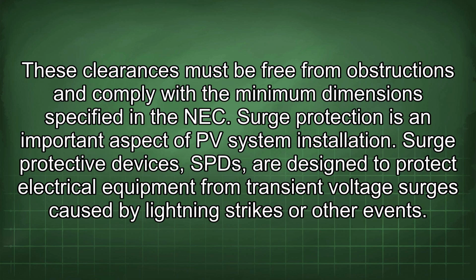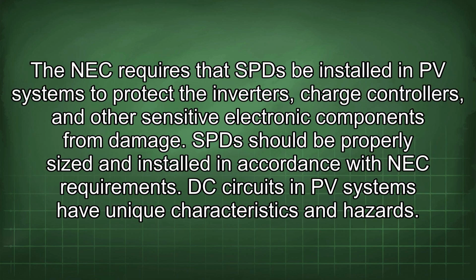Surge protection is an important aspect of PV system installation. Surge protective devices, SPDs, are designed to protect electrical equipment from transient voltage surges caused by lightning strikes or other events. The NEC requires that SPDs be installed in PV systems to protect the inverters, charge controllers, and other sensitive electronic components from damage. SPDs should be properly sized and installed in accordance with NEC requirements.